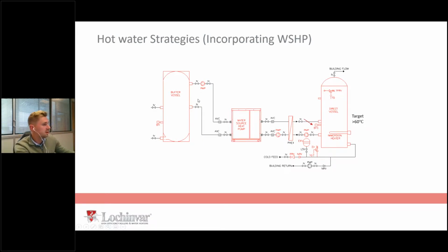It's a water source heat pump picking up from a thermal store. That thermal store could be picking up from anywhere, but typically it's an ambient loop. Ambient loop in a building's running at like 45 degrees or 30 degrees or whatever it may be, blending to 35. The water source heat pump picks it up, generates hot water in a local area with a local efficiency in excess of 500%, which is massive.